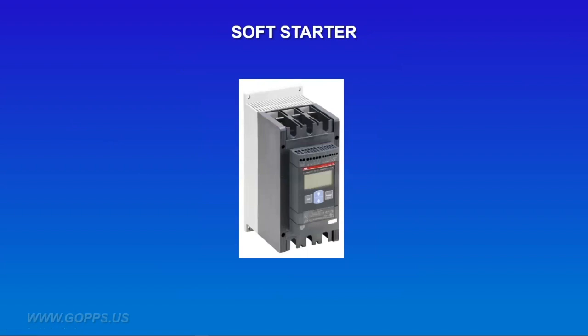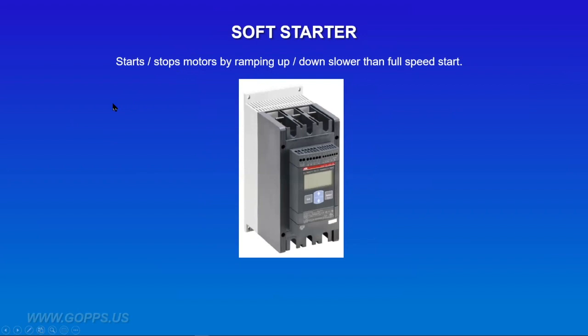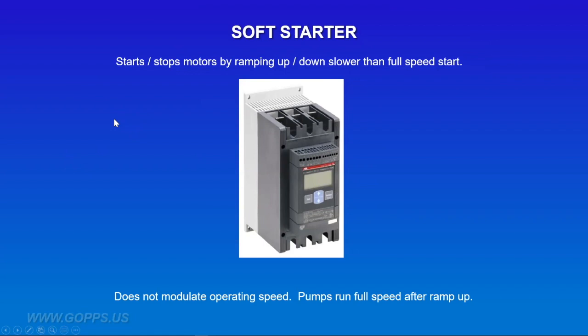A soft starter is a device that starts and stops a pump by ramping it up and down slower than full speed. When pressure drops, the pump ramps up slowly; when pressure reaches a set point, it ramps down slowly. This is easier on the pump and on the pipes and fittings in the field. However, it does not modulate operating speed — once it ramps to full speed, it stays at full speed. The only other option is that when pressure reaches a certain point, it ramps back down and stops.